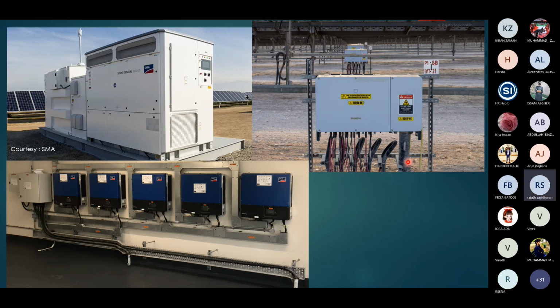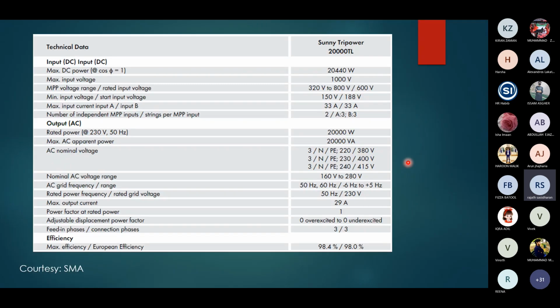Anyways, if you look into the data sheet of a typical inverter, whenever you get time, please browse for more and try to identify. You can see the details, okay? There are a few key things that we as designers look into: what is the maximum voltage range in MPP conditions? What is the maximum open circuit voltage range? So you can see here that the maximum is 1000 volts, and the MPP voltage range is 320 to 800.